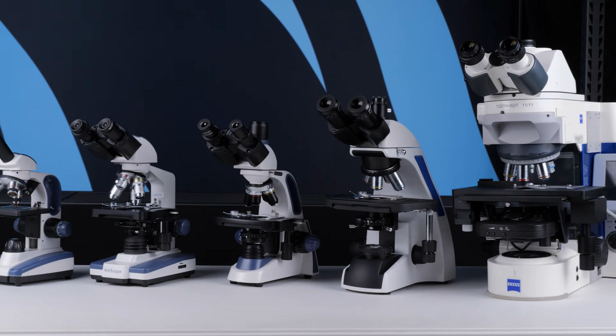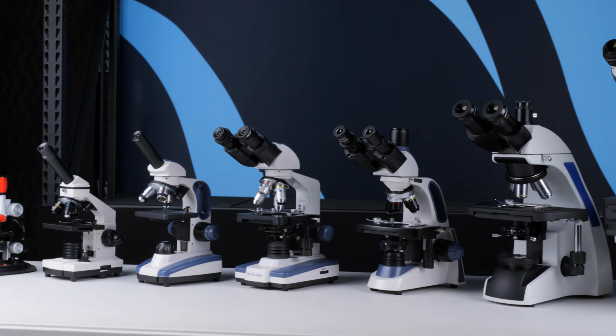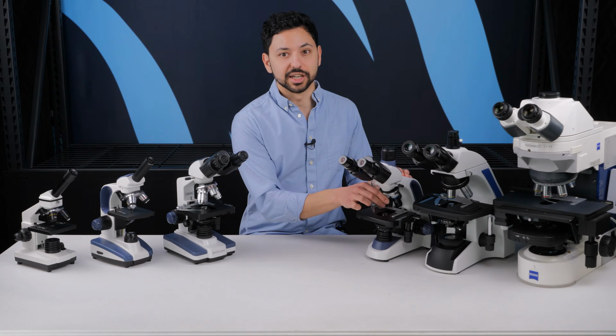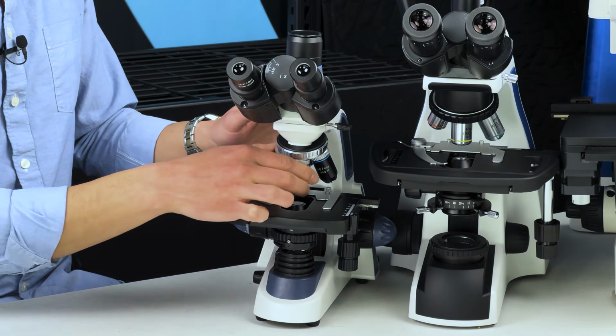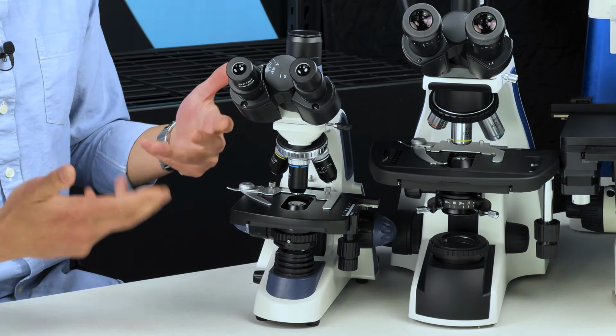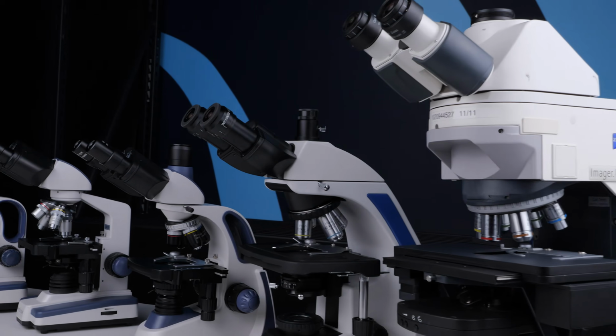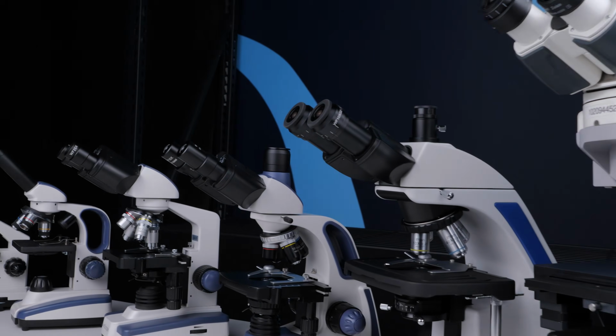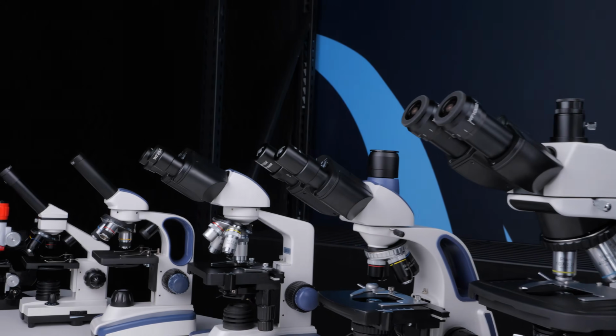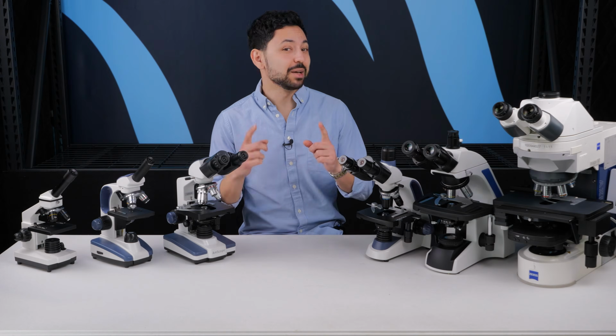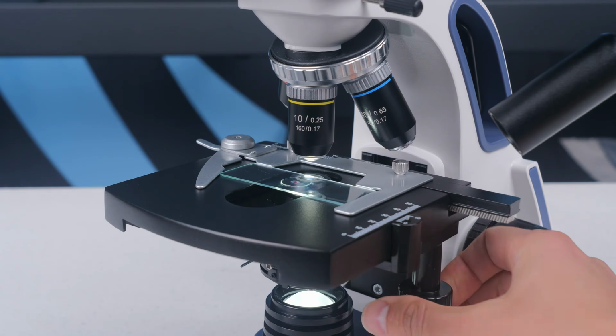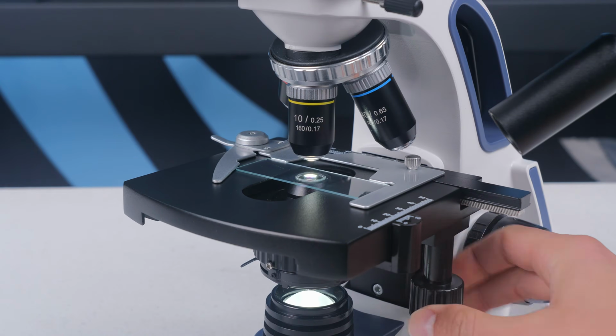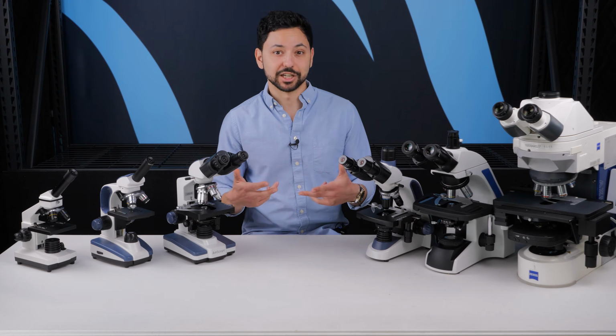Compound microscopes are defined by their compound objectives, usually on a rotating turret. If you want to go up in magnification, you have to rotate up a higher magnification objective. Compound microscopes are the most sophisticated of all of the microscope categories that we've talked about thus far. And really, the more money that you spend, usually the more capabilities you get, such as having a condenser or having a mechanical stage, rather than getting better image quality or more magnification per se.